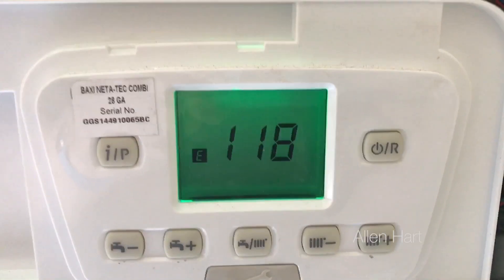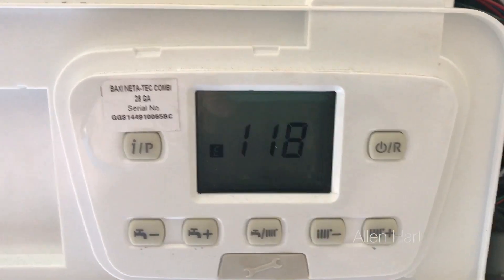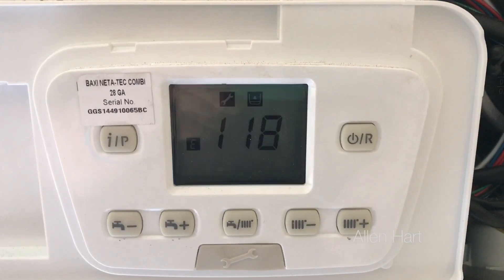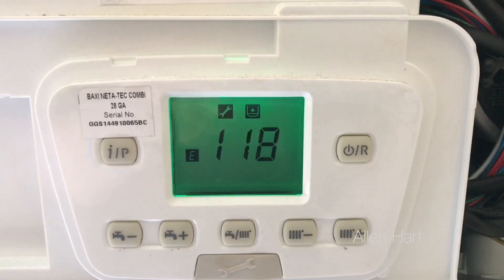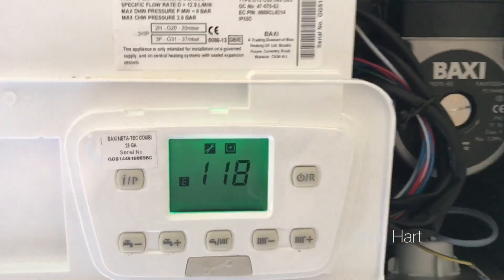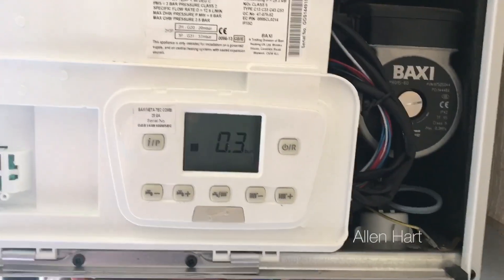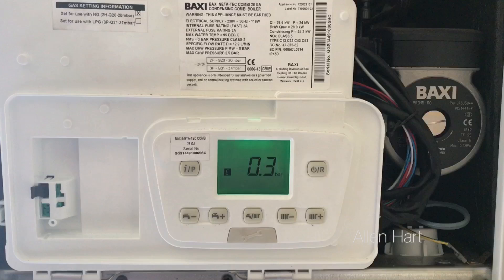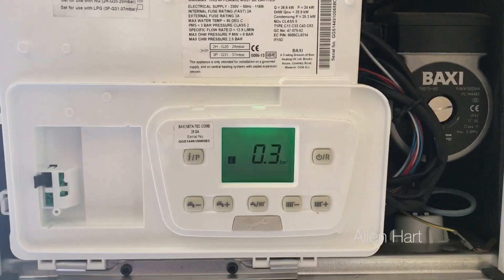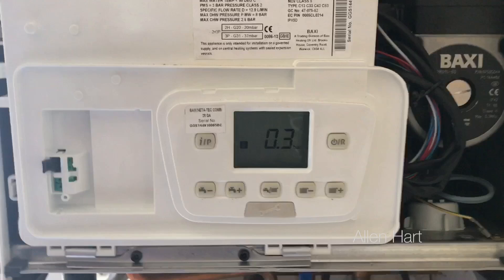My name is Alan Hart and today we're going to show you how to re-pressurise a Baxi Neta-Tec combi boiler. The front display is flashing, showing 0.3 and 118, which means low water pressure on this particular combi boiler.